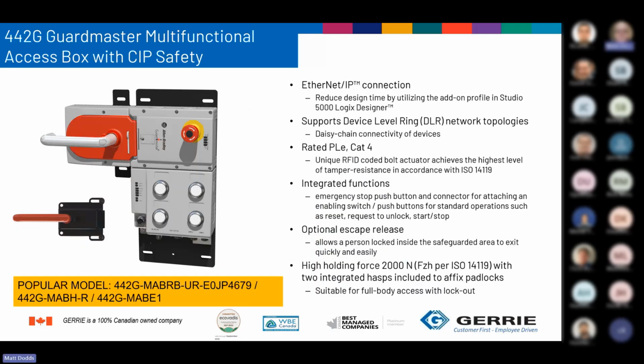As wonderful as it is, sadly, the 440G MZ cannot satisfy all applications. The 442G MAB, or multifunction access box, provides local door access and control of guarded space. There are 2 versions. The Ethernet IP is the version I recommend. It reduces design time by using add-on profiles in Studio 5000. It supports DLR. It's rated PLe Cat 4.